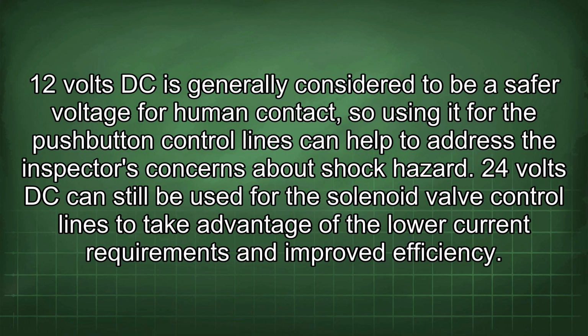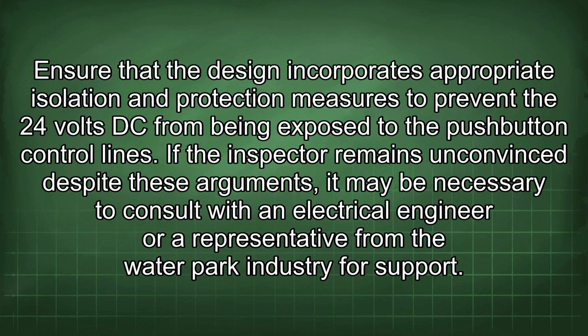12 volts DC is generally considered to be a safer voltage for human contact, so using it for the push-button control lines can help to address the inspector's concerns about shock hazard. 24 volts DC can still be used for the solenoid valve control lines to take advantage of the lower current requirements and improved efficiency. Ensure that the design incorporates appropriate isolation and protection measures to prevent the 24 volts DC from being exposed to the push-button control lines.